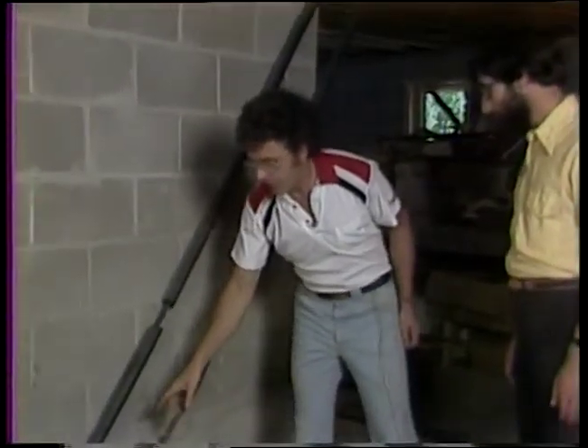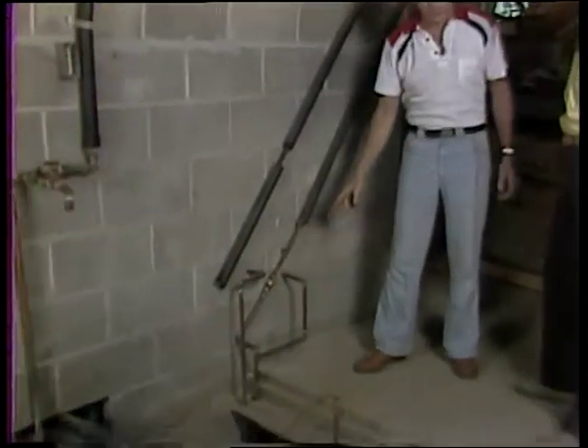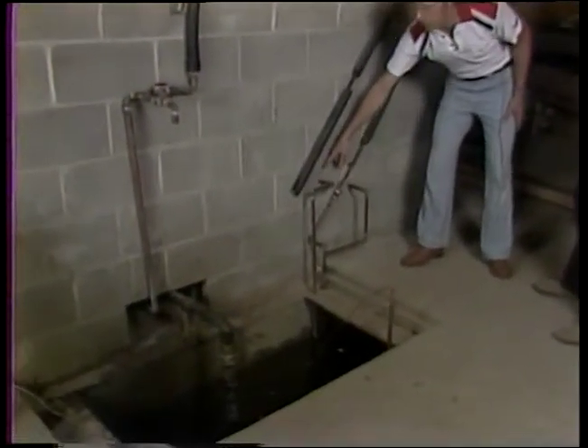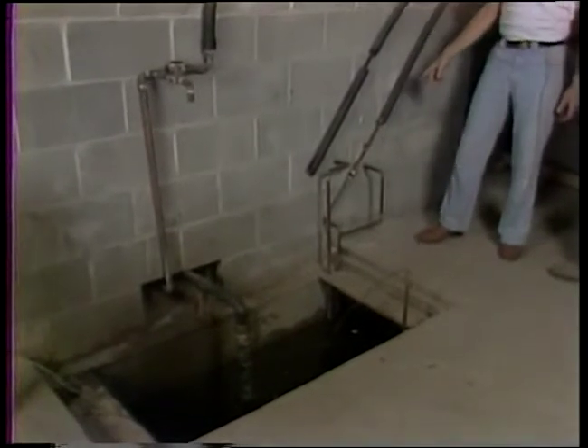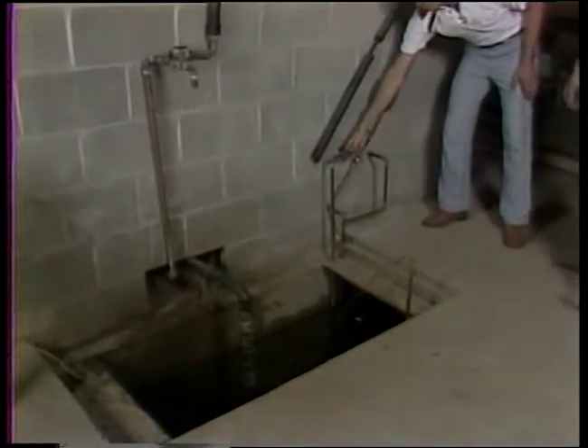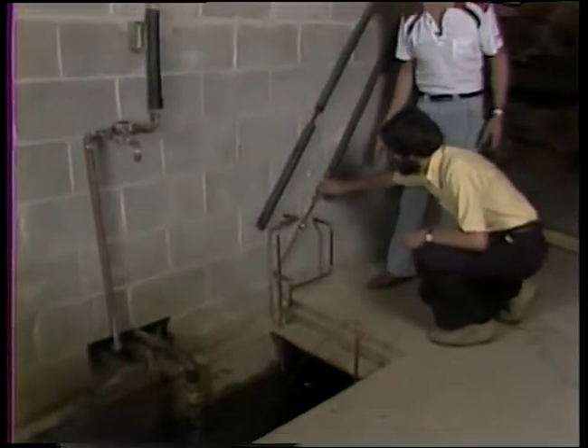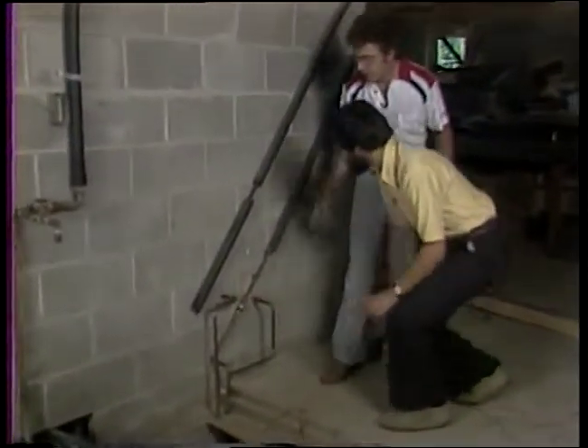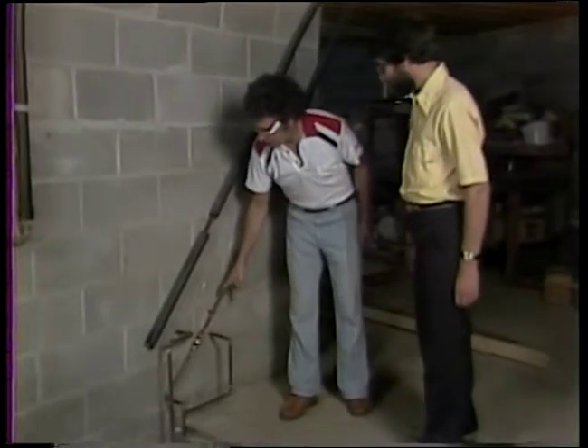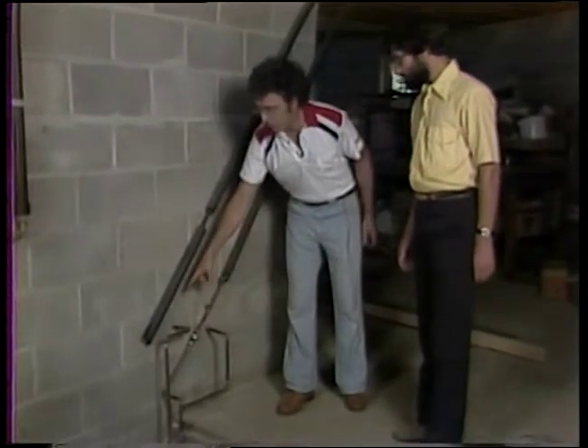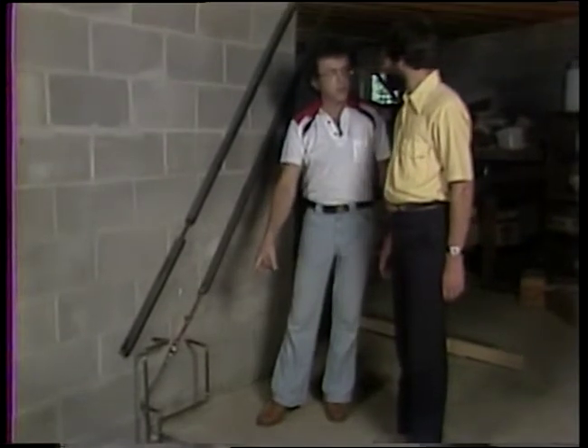Okay. These are the pipes that come in from the collectors on the outside. We're down in the basement presently. And the fluid that flows through the collectors comes down this particular pipe, flows down into this large tank through a heat exchanger, and then back up through this pipe into a circulating pump in the other room. If you would feel this particular pipe and this one, you'd notice there's about a 40 degree temperature differential because it's operating presently. Okay, the heat that flows through this particular pipe and back in through the pump then is transferred to this large underground storage tank.